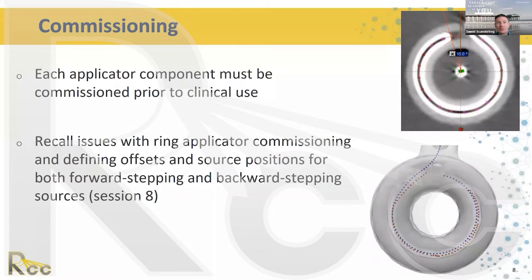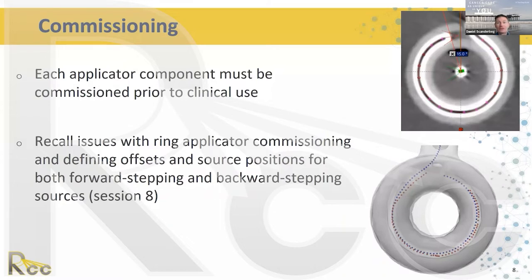It's critical to commission and test each applicator component prior to clinical use. Ideally you should characterize and test each component and perform an end-to-end test with all staff involved so everyone gets comfortable with the procedure and can respond to any issues. This includes the physician assembling the applicator, placing it in a phantom, taking an imaging scan, transporting to the treatment area, and planning and delivering the treatment. Emergency procedures can also be discussed during a debrief. For ring applicators in particular it's especially important to commission the ring since the source path can lead to uncertainty in positioning.